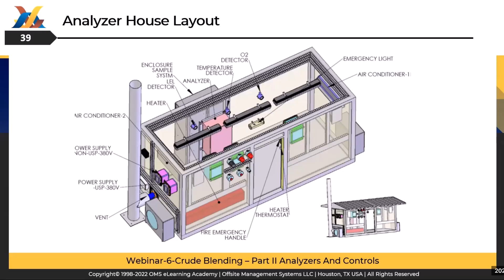The system is typically equipped with facilities, and you can see them in the picture: air conditioning, power distribution, lighting, termination and junction boxes, gas and flame detectors, relevant piping and wiring. Process sampling probes, which cannot be seen here. Also sample transport lines and a sample conditioning system, which is designed to provide the sample in a condition compatible with the measurement techniques used by the analyzers, which are installed inside the shelters. And additional peripheral equipment like sample recovery systems, stream selection facilities, internet connection, and so on. Next slide, please.